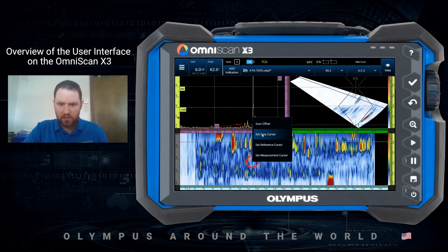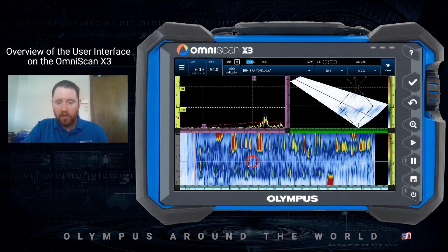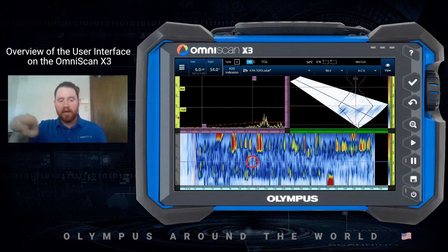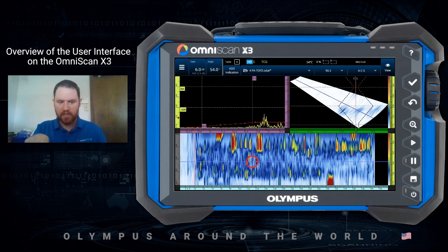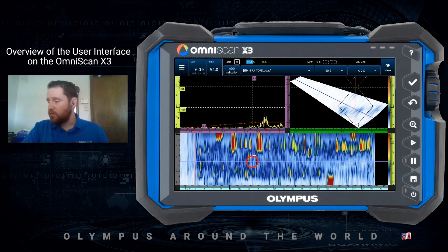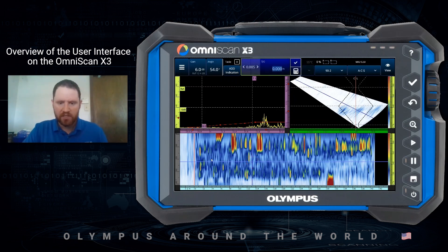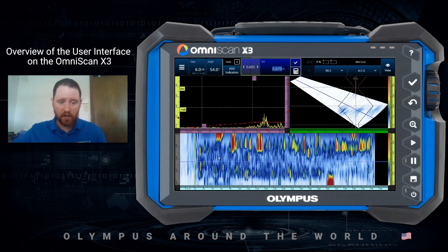You'll notice different menu options when you hold your finger down in certain locations. One of those is to set your data cursors. If I select that, it will place the data cursor in the C-scan display directly in the center of that target. This gives me a feedback loop confirming the touch screen is functioning correctly and provides accuracy in knowing exactly where the cursor will go. The touch screen also functions for clicking on a cursor or a gate and then using the wheel to move the location of that cursor, gate, or angle.